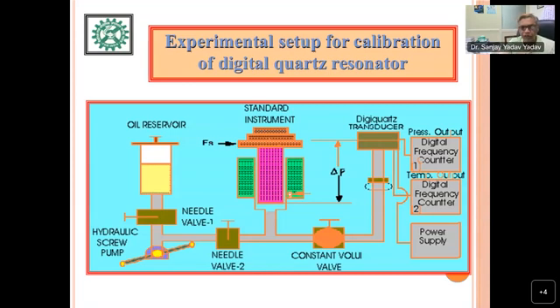The fixed value of the transducer is very, very difficult in digital gauges because of Boyle's law, this pressure relationship with temperature and volume change. The stability of the transducer reading is very, very difficult. So personally, I always recommend you put some fixed mass at the deadweight tester and see the transducer reading. And then on the same masses, you take repeated measurements at the transducer with varying environmental conditions, and then make the fitting of the data to see the behavior of the gauge. So that way, this method is very, very good. But I am not stopping you from using another method also, if you can fix the value of the transducer, but it is very, very difficult.